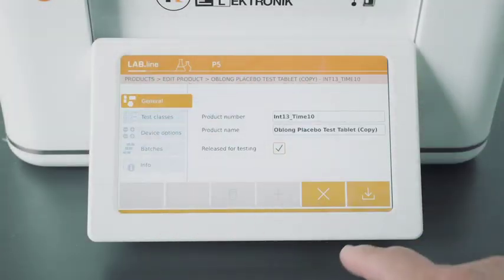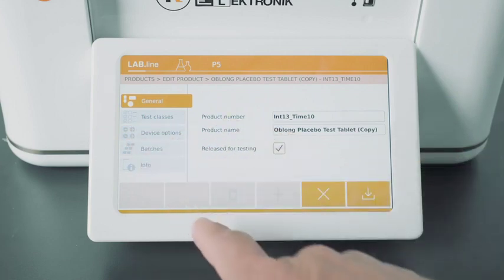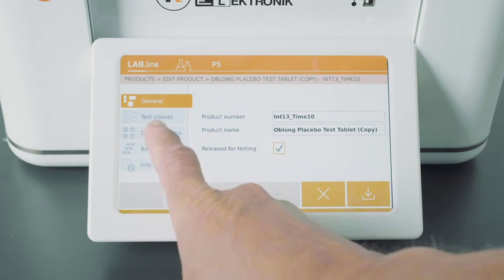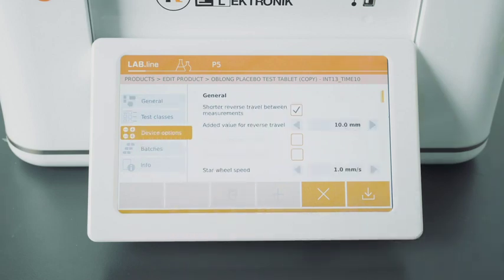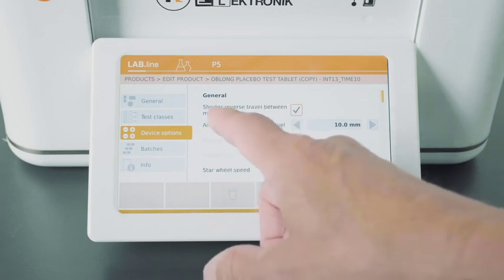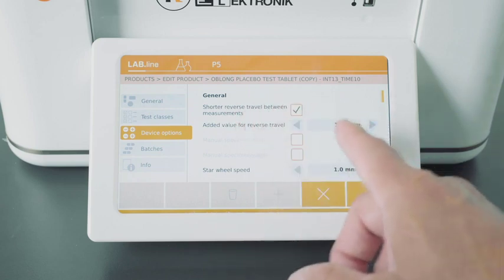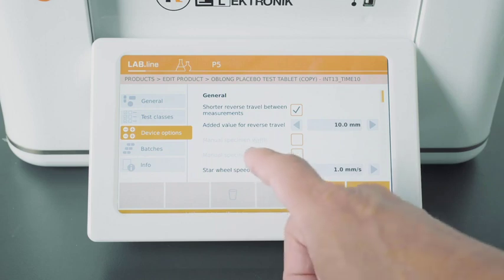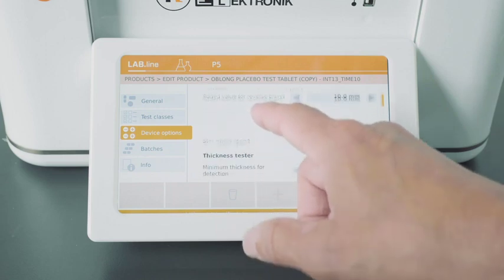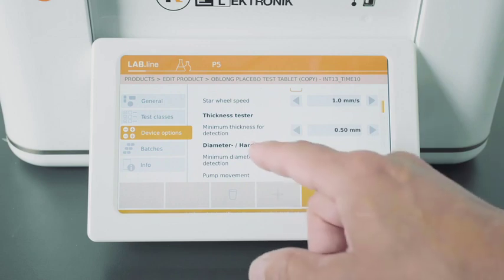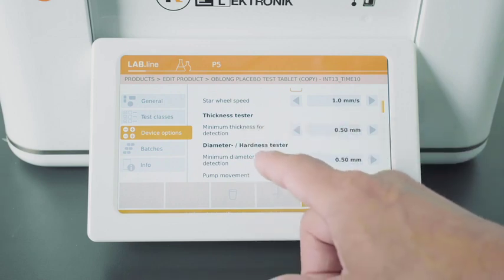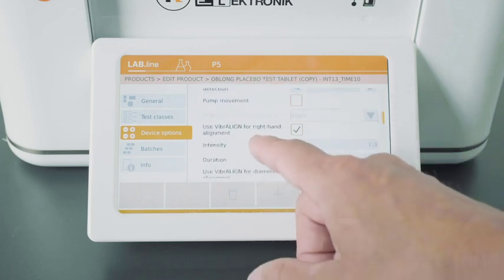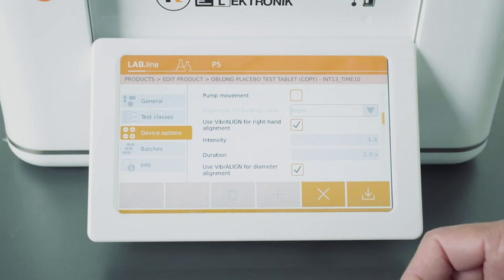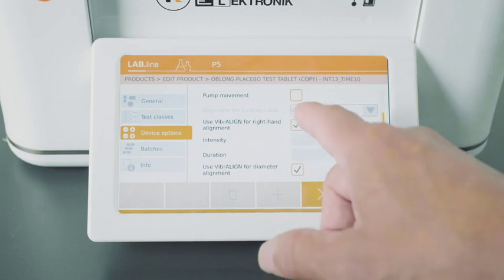And we have already one oblong tablet entered here. And the only difference is in the device options. There we need to enter a few additional specifications. One is shorter reverse travel between measurements, that's recommended. You can add 10 millimeters, that is as a standard, that's fine. Then the star wheel speed we can leave at 1 millimeter. Minimum for thickness and diameter testing is the same. In some cases where oblong tablets tend to tilt during the width measurement, you can activate the pump movement.